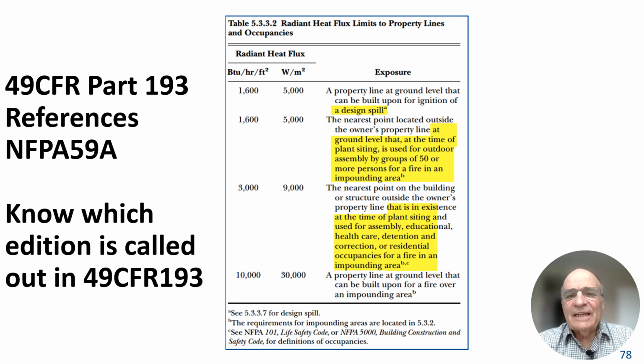Now let's talk a little bit about siting an LNG plant. And this has to do more with design engineers understanding how to site an LNG plant rather than how to operate an LNG plant. But operators should at least be aware of this information. 49 CFR Part 193 references NFPA 59A. NFPA 59A is a consensus code, which means you are not required to abide by NFPA 59A, except for the fact that it is referenced by 49 CFR Part 193. That means that because of Part 193, NFPA 59A is required to be used by LNG operators as a code of operation for LNG facilities.